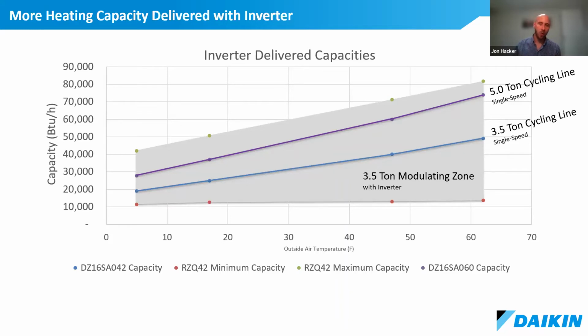This is what we're showing graphically here. We've got the same modulating zone, same exact equipment that I showed before, and the same blue line for the cycling line for that 3.5 ton piece of equipment. They're just overlaid on the same graph here. The point I want to drive home is that the 3.5 ton single speed product, when it's 5 degrees outside, looks like maybe it can deliver 20,000 BTUs and that's it.